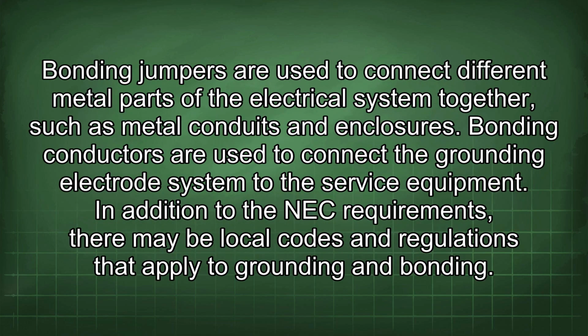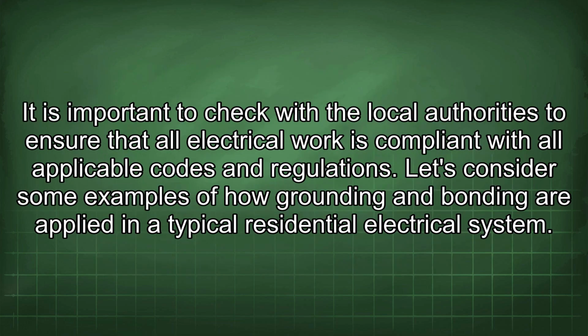Bonding jumpers are used to connect different metal parts of the electrical system together, such as metal conduits and enclosures. Bonding conductors are used to connect the grounding electrode system to the service equipment. In addition to the NEC requirements, there may be local codes and regulations that apply to grounding and bonding. It is important to check with the local authorities to ensure that all electrical work is compliant with all applicable codes and regulations. Let's consider some examples of how grounding and bonding are applied in a typical residential electrical system.